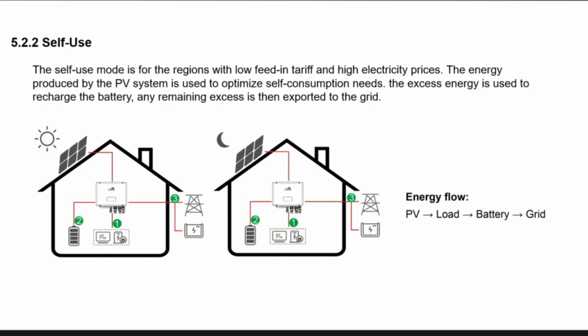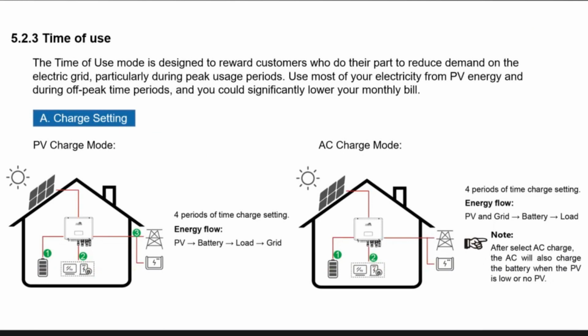But the battery is always charged before it's converted to AC, right? So it goes to the MPPT, it doesn't go to the AC first and then back from AC to DC. Yes, it will charge directly from the MPPT to DC. It checks the load, and then charges the battery directly from the MPPT. The first priority is the load, because the inverter is equipped with a smart meter or CT, and it will detect the energy direction. That's the most efficient, otherwise you would be converting twice. Exactly, it will not charge from the AC side because the energy would be converted again. So it checks the load, and otherwise charges the battery directly from the PV side.